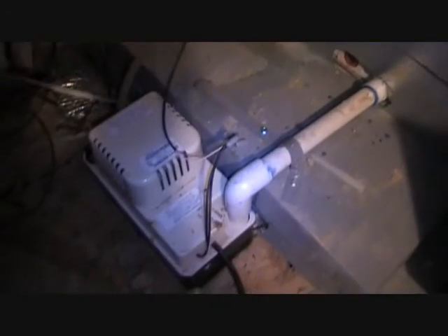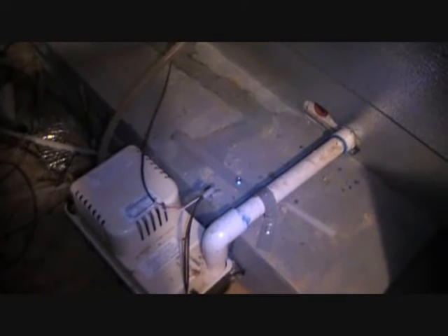You can see where they routed the hose here from the condensate pump is pinched. Now at some point, this is likely to kink, and I'm sure that it's stressing the pump so that it will shorten its life. And speaking of shortening the life, all of these things that I'm pointing out will shorten the life of your equipment. So shoddy workmanship and a cheap, I don't mean inexpensive, but cheap installation really does cost you more in the long run. It costs you more in higher utility bills. It costs you more in system maintenance, system repairs, and will also make it so that you have to replace your system sooner.